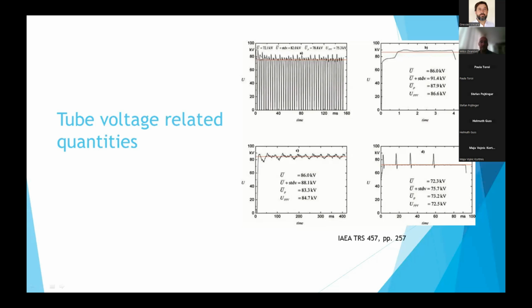Ideally, we of course want to use only one number to represent tube voltage, but tube voltage is a function of time. So in order to use only one number, we can define different quantities. For example, we can define average voltage, just calculate the average value over time. We can look at the peak voltage, so the maximum peak voltage, which is the maximum value during an exposure, or we can look at different peaks and then calculate the average peak value. So there are different quantities, and they have different values.